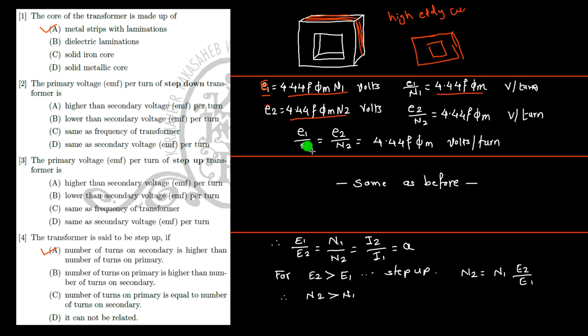Here you can observe that E1 by N1 equals E2 by N2 equals 4.44 F phi m. This indicates that the voltage per turn on the primary and the voltage per turn on the secondary is the same. So the primary voltage per turn of the step down transformer is same as the secondary volt per turn.